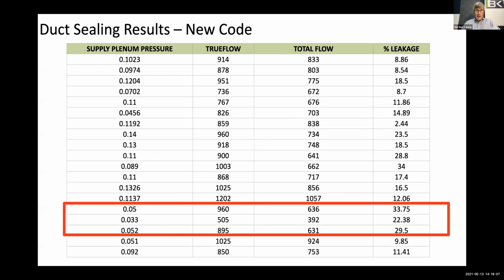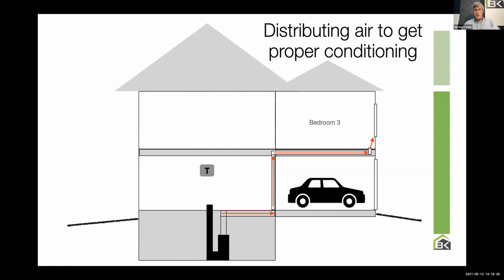because that room over the garage needs 66 CFM. And if you're losing 20% along the way, and wouldn't you know it, that's the longest run, so it loses more than the one going to the dining room. Duct leakage doesn't hurt you in the dining room, but it sure hurts you in the room over the garage, where the air is going through a long duct and out through the insulation and so on. You want to get your duct leakage under control.